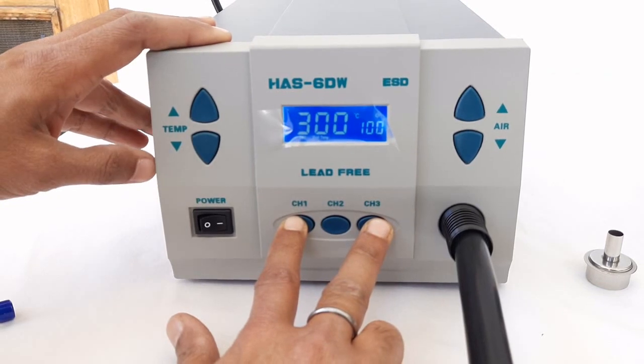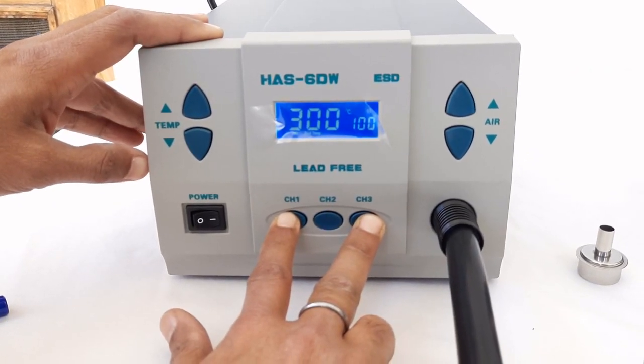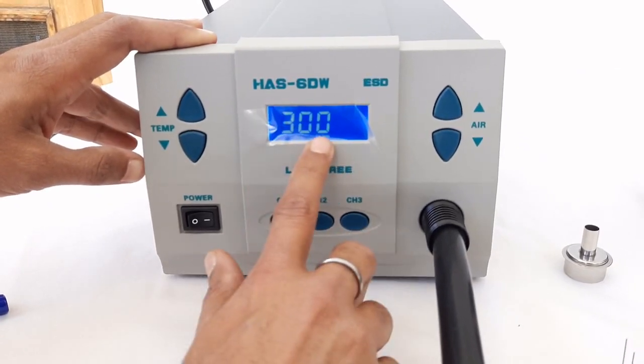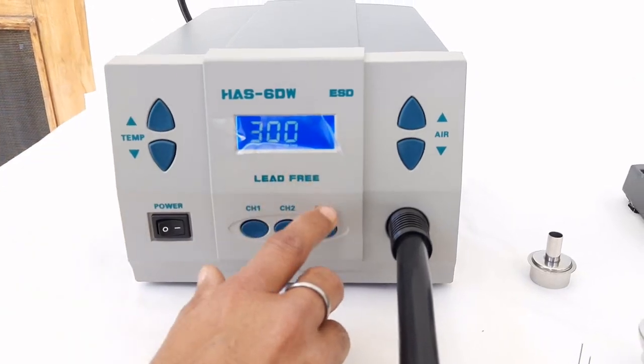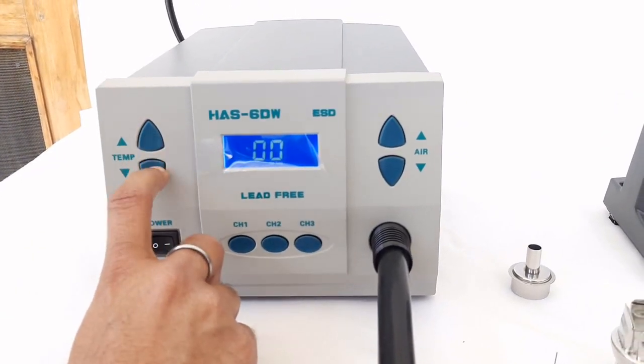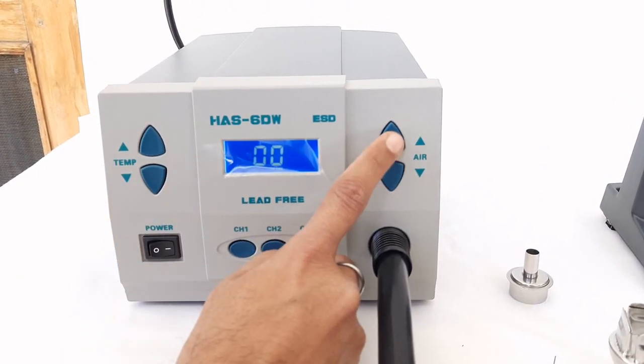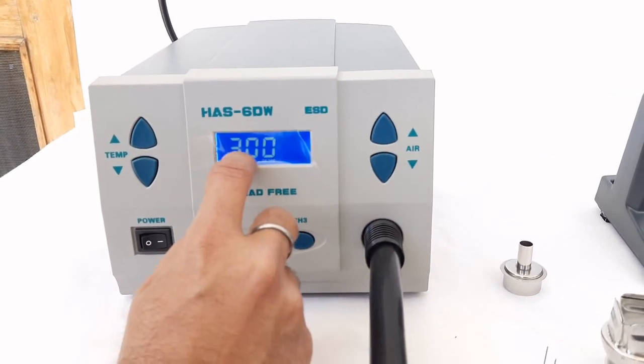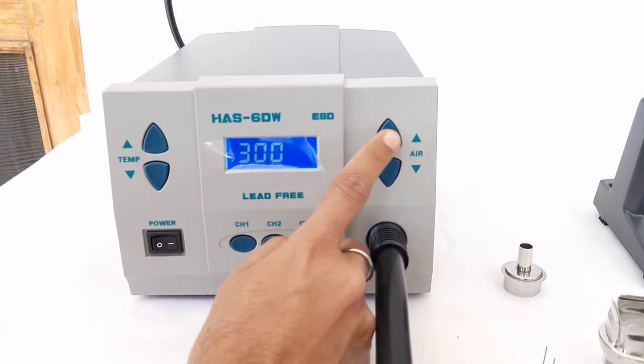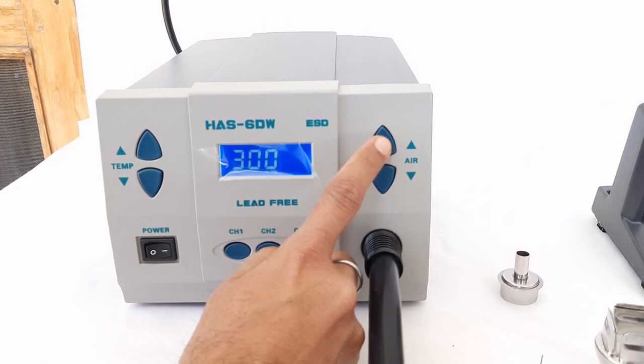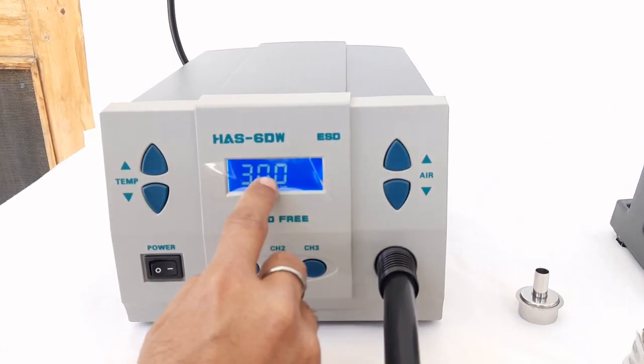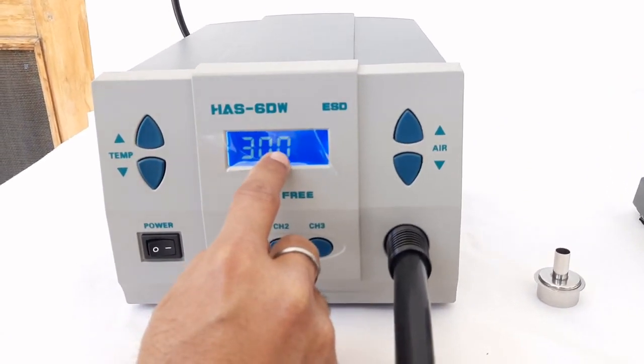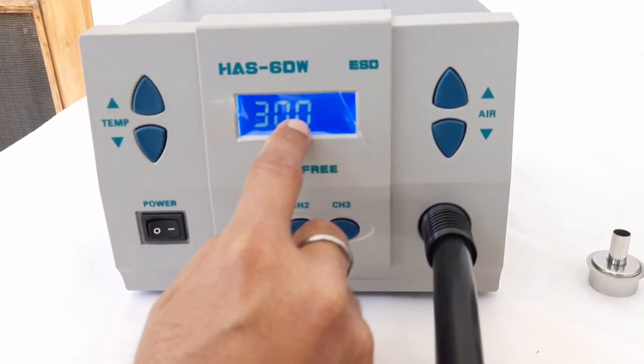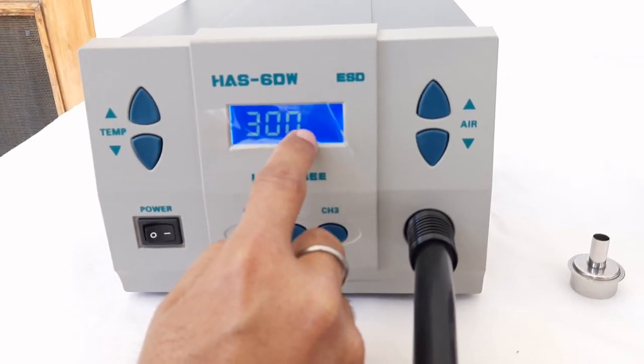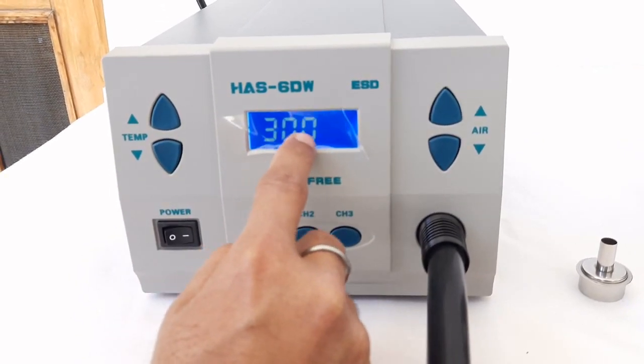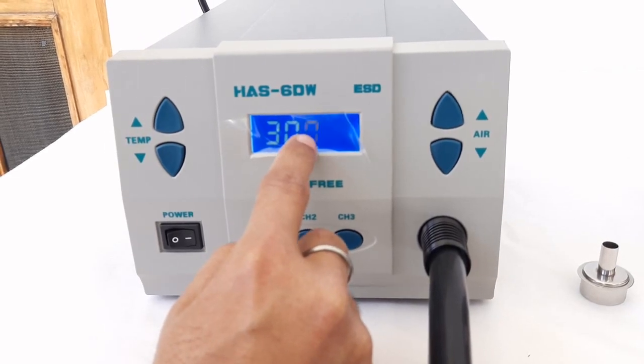After 15 seconds it will enter into the calibration mode, and we can just with the help of this temperature key, up down key, and this to move the cursor further, we can use this hot air key, and we can just enter the value which we have observed on the external calibrator, and this is how the calibration is done.